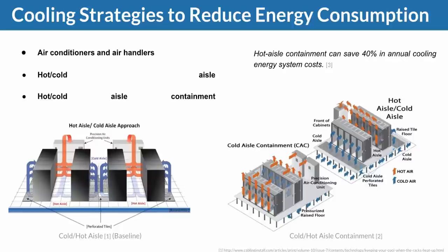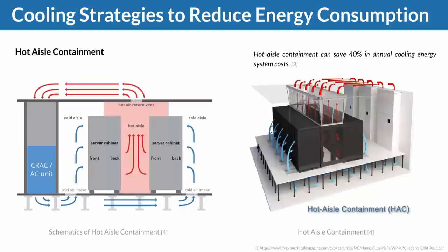Or there's the second approach where we are containing the hot aisle, simply creating a big channel of hot air that is being directly pushed into the cabinet that drives the flow out and processes the air. So this is another look at the approach of contained hot aisle. We are not allowing the hot air to recirculate. We are building some kind of a barrier. And it actually doesn't have to be a very thermal resistant one, although this might also help if we are really concerned about potential heat losses within such a system.